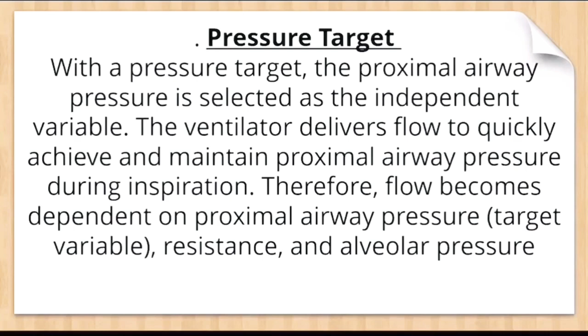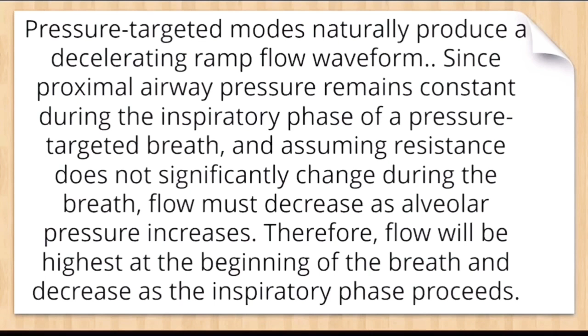Now pressure targeted modes naturally produce a decelerating ramp flow waveform. Since proximal airway pressure remains constant during the inspiratory phase of the pressure targeted breath, and assuming the resistance does not change significantly during the breath, flow must decrease as alveolar pressure increases. Therefore, flow will be highest at the beginning of the breath and decreases as the inspiratory phase proceeds. That is what I described earlier. That is the decelerating waveform pattern, where the flow abruptly increases initially and then decreases slowly to the zero level.